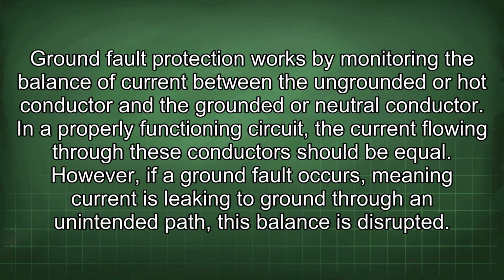Ground fault protection works by monitoring the balance of current between the ungrounded or hot conductor and the grounded or neutral conductor. In a properly functioning circuit, the current flowing through these conductors should be equal. However, if a ground fault occurs, meaning current is leaking to ground through an unintended path, this balance is disrupted.